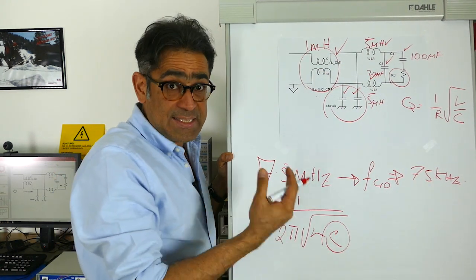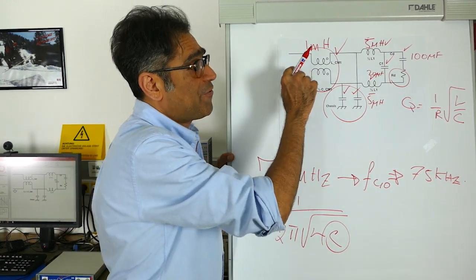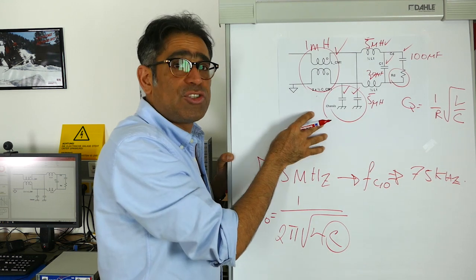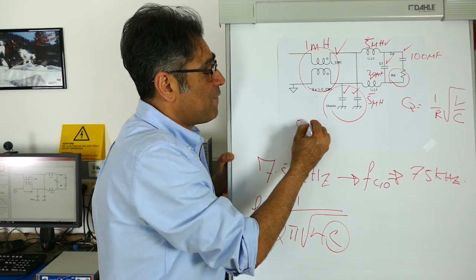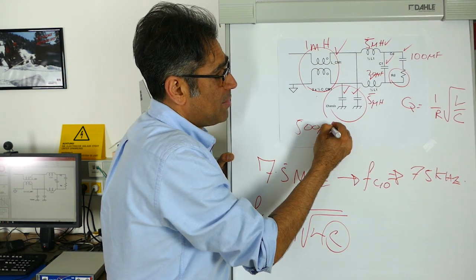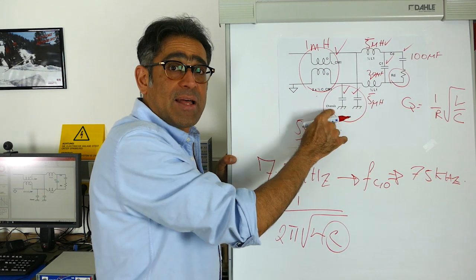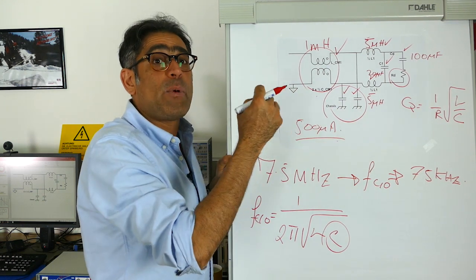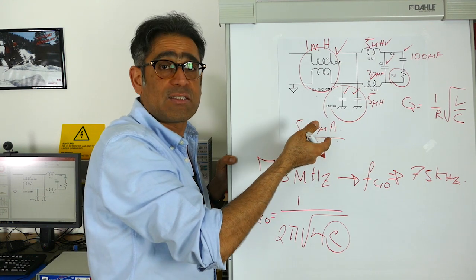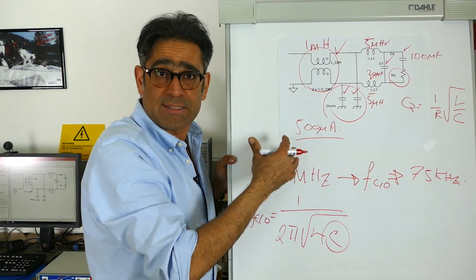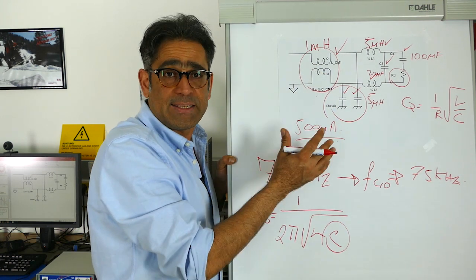In the case of AC line filters, there is an extra requirement because the leakage current from your line and neutral down to chassis is limited. Depending on the standard, this could be, for example, 500 microamps. In that case, you calculate the size of the capacitors based on how much current will flow through them to chassis, and you cannot exceed that limit. This gives you a second way of calculating and ensuring that the capacitor values do not violate any of the safety criteria.